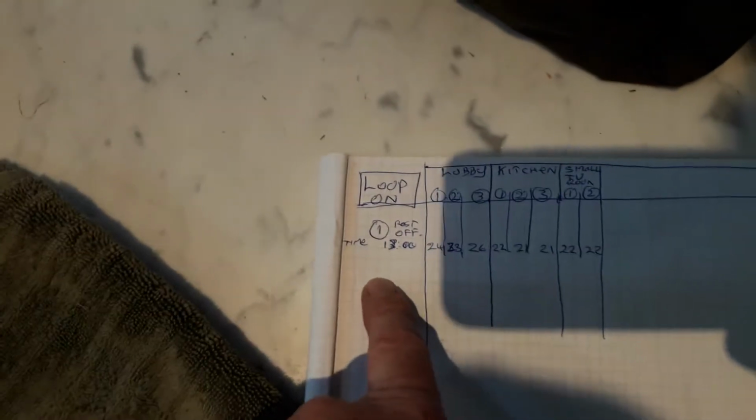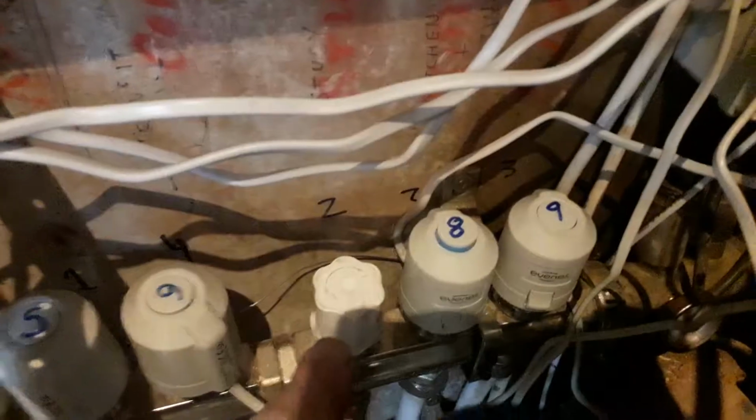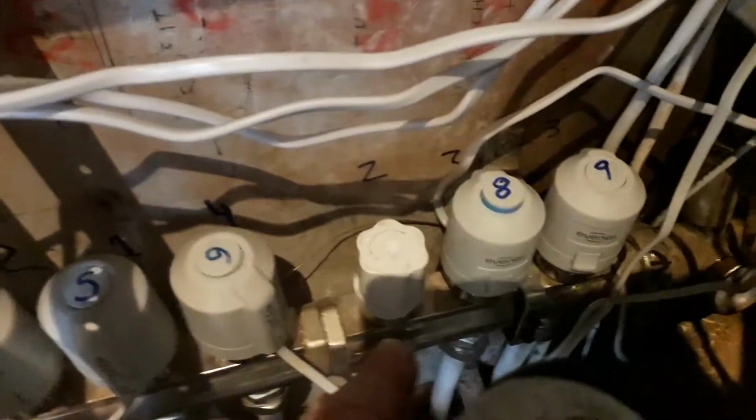So now if we have only loop 8 on, we can tell, as we did before, which part of the floor the temperature rises on, and then we can mark in loop 8 wherever it is in the house. And we just continue that process. When we've got 8 done, we can take the actuator head off that, put this mechanical piece over there and do 7, and continue on down along either 1 to 9 or the other way around.